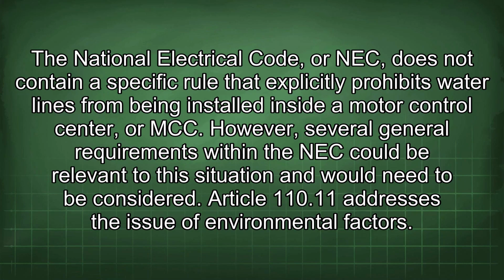The National Electrical Code, or NEC, does not contain a specific rule that explicitly prohibits water lines from being installed inside a motor control center, or MCC. However, several general requirements within the NEC could be relevant to this situation and would need to be considered.